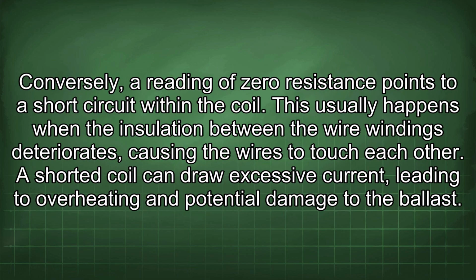Conversely, a reading of 0 resistance points to a short circuit within the coil. This usually happens when the insulation between the wire windings deteriorates, causing the wires to touch each other. A shorted coil can draw excessive current, leading to overheating and potential damage to the ballast.